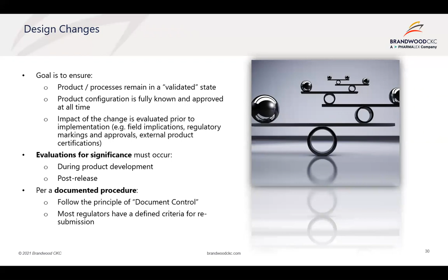So as I mentioned, the evaluation for significance of each change must occur during product development, but also post-release, and that has to be done as per documented procedure. So that obviously follows the same principle as for your original design controls. And an important point to note here is that depending on the jurisdiction or the country where your product is going to be released, the regulators may define different criteria for what they view as being significant and require notification prior to implementation. So you must incorporate those guidance documents, such as FDA guidance documents, TGA changes within your internal procedures.